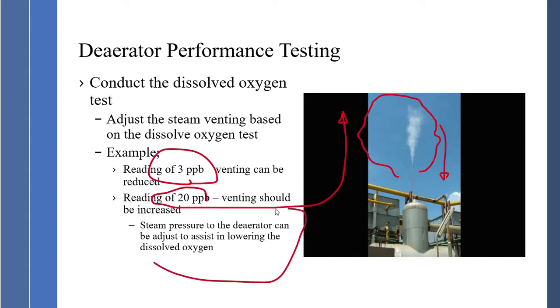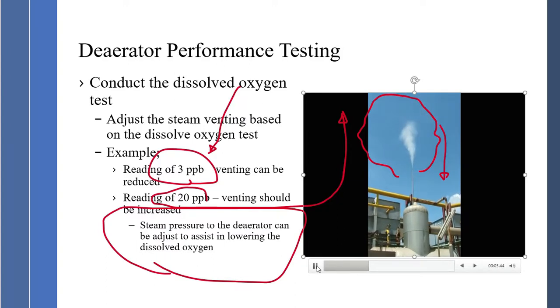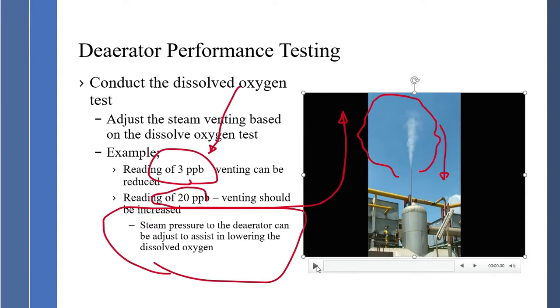The other thing you can do is adjust the steam pressure. People say the deaerator should operate at 5 psi, some say 8 psi, others say 12 psi. What is the correct pressure? The correct pressure is whatever achieves below 7 parts per billion. So I can adjust pressure and venting to make sure I achieve 7 parts per billion or below. In one case, venting was too aggressive — it was reduced, and a good amount of energy savings was accomplished.